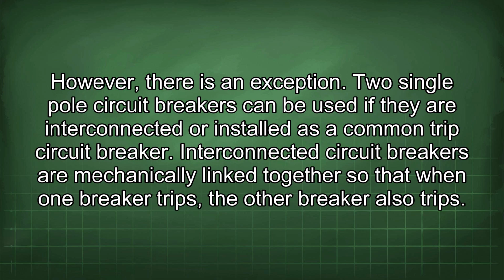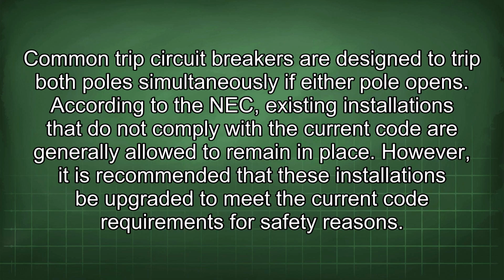Two single-pole circuit breakers can be used if they are interconnected or installed as a common trip circuit breaker. Interconnected circuit breakers are mechanically linked together so that when one breaker trips, the other breaker also trips. Common trip circuit breakers are designed to trip both poles simultaneously if either pole opens.